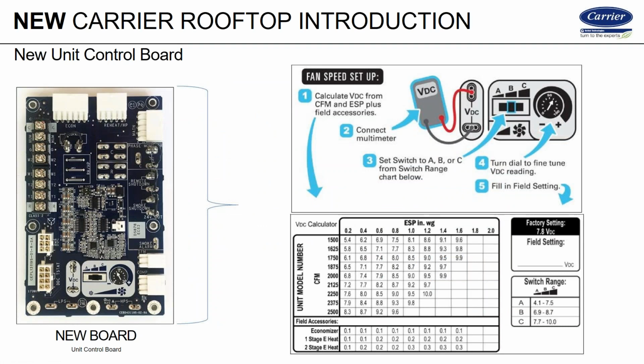So it's just that easy to set these dip switches up. That's all there is to it. Once you get your arms around that, it's very straightforward. It's quick. The hardest thing to do, the most time-consuming thing, is to take your static pressure, which is something we should have been doing all along, even with the belt drive units. It's the right way to do it.